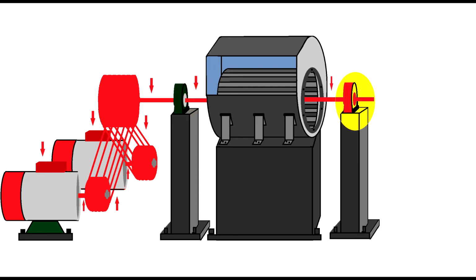If you use the second plummer block, which we'll see now in red color, that's the worst fault you can have, because you will apply a lot of stress onto the shaft. The motor will try to turn the fan, but that won't be possible because the bearings are gone.